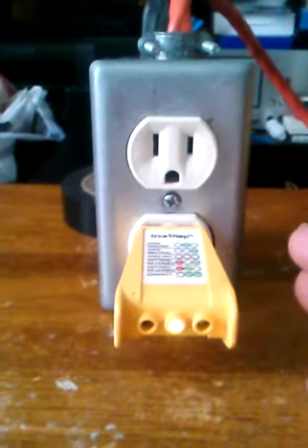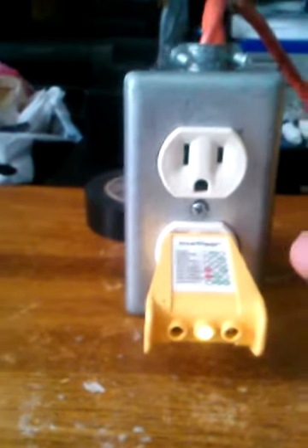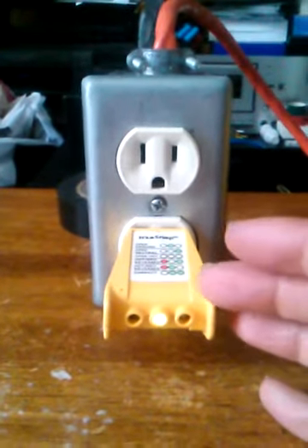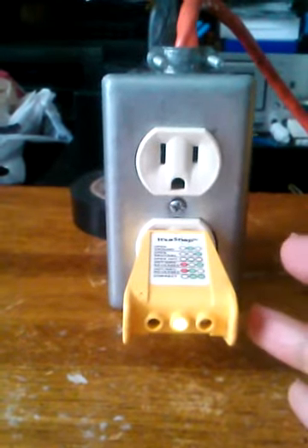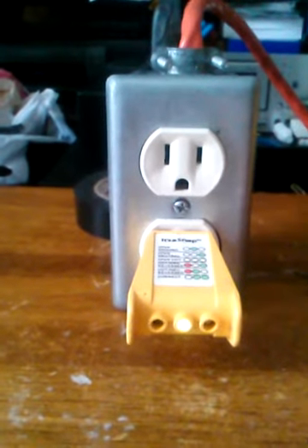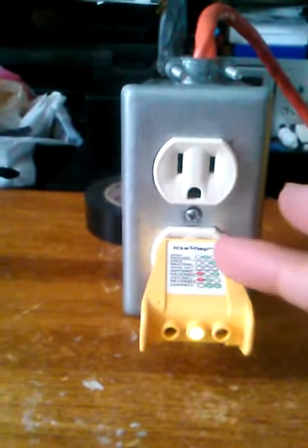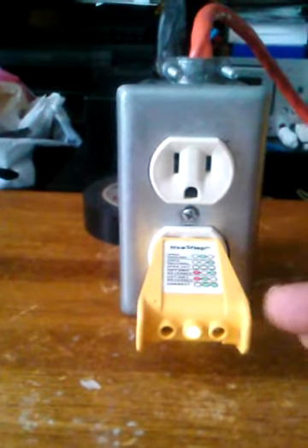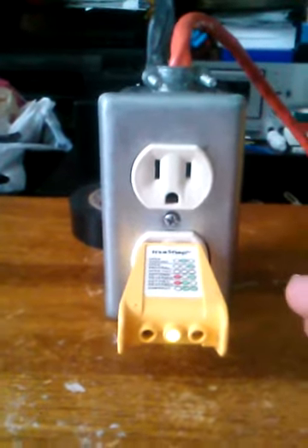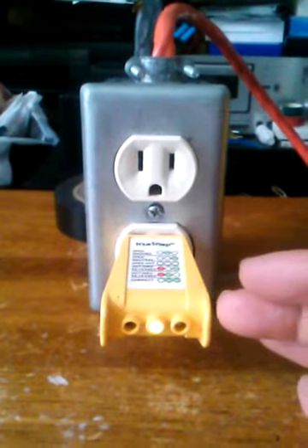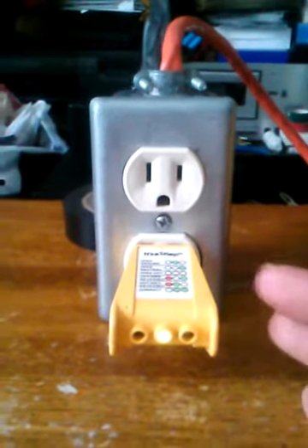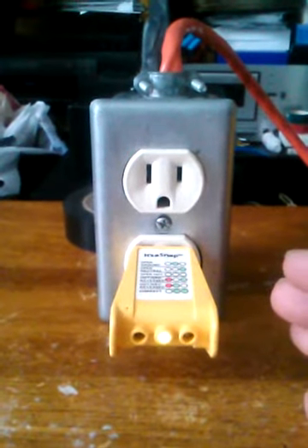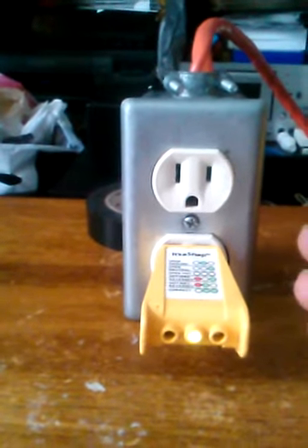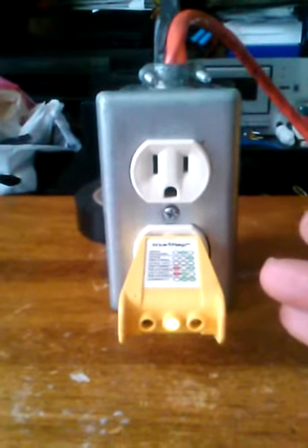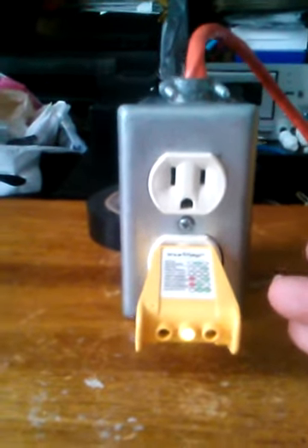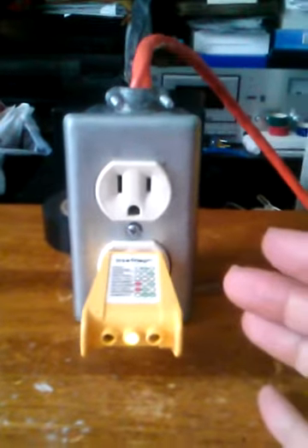Or if you have a home that has Romex wiring, or a building that has Romex wiring that doesn't have a ground, it's going to open up as well with an open ground, which is no good for computers either, because if there's a short circuit in the system, it needs something to go back. It needs something to short back to ground, either the hot or the neutral side, if the outlet happens to be reversed. And without the ground, there's no way to send back that short circuit to the service panel of the electrical circuit to trip it. So it will prevent any further current to that outlet, which will cause serious problems like fires in some cases.